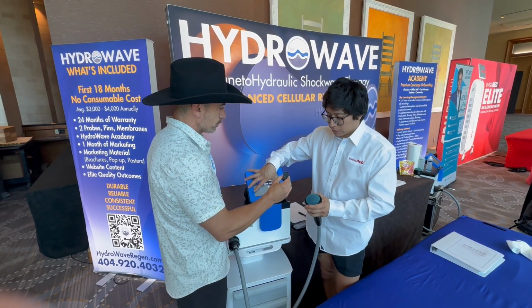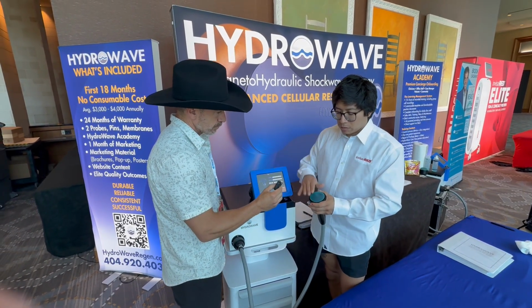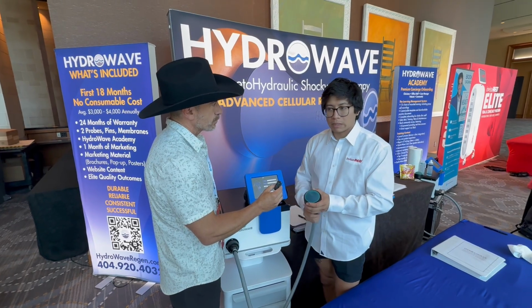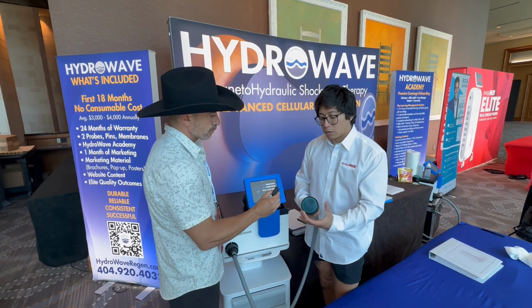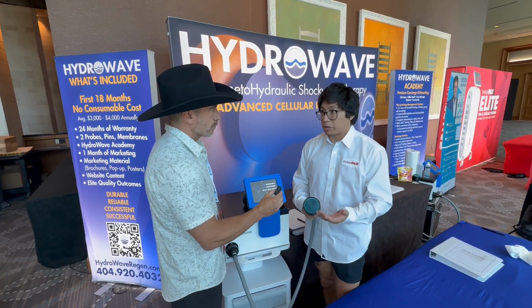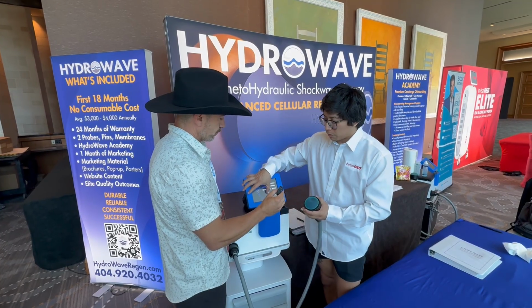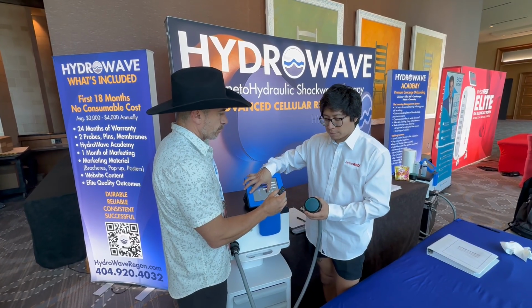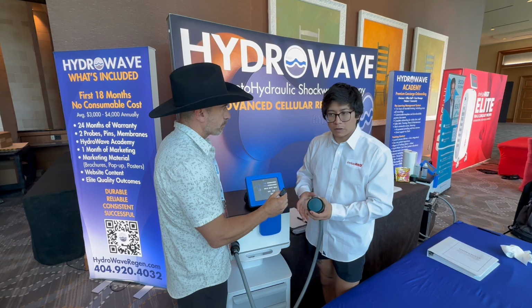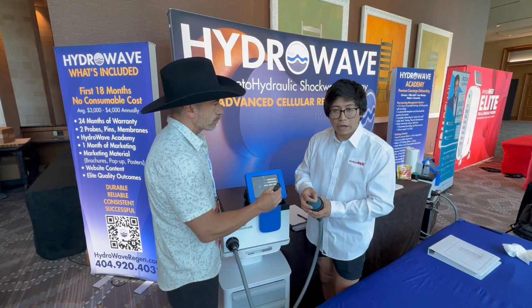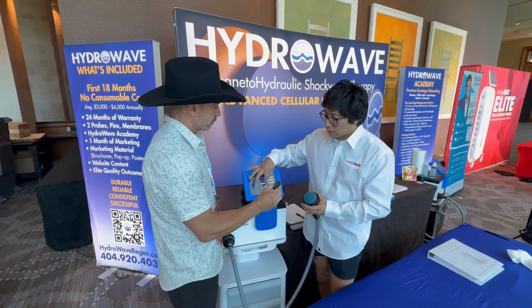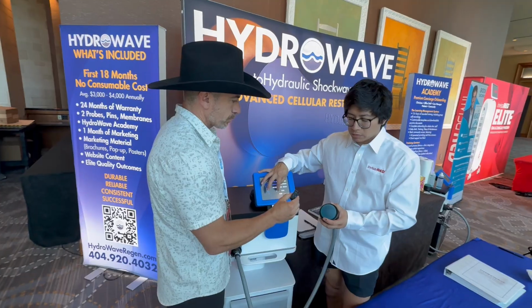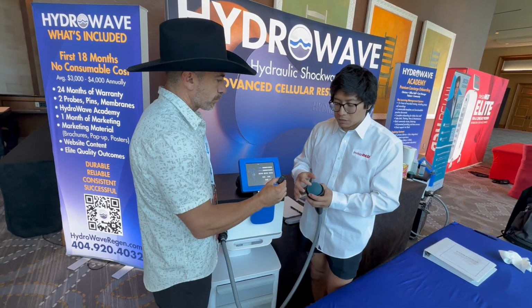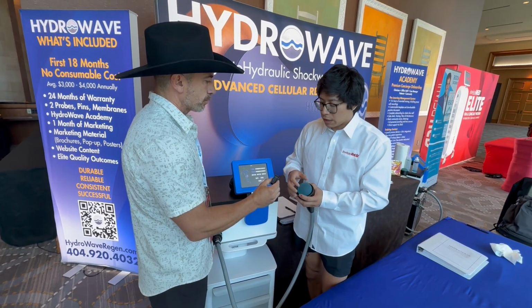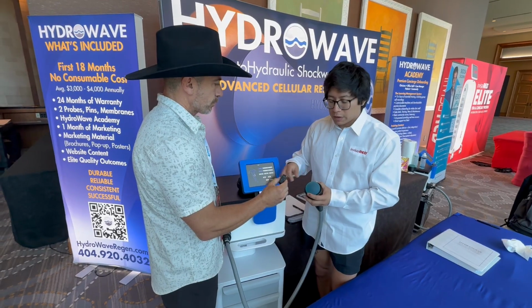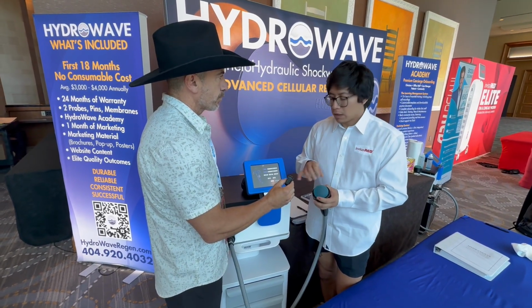Right now I can drain the head, which gives more of a broader spectrum, but because the wave is still going out, you'll get deeper penetration into the area. If you fill up the head with more water, it's going to diffuse that cone of the focused shockwave to a pinpoint area—probably the smallest, if we fill this up completely, is more like a dime-size area of treatment. If you fill it up more, you can even get it smaller than that.